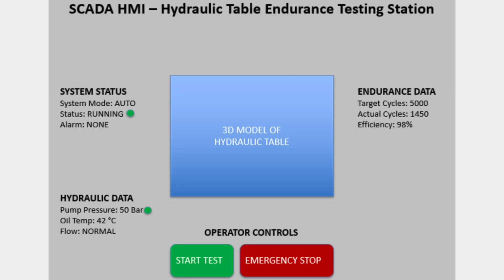Hello, I'll be presenting about the human machine interface of our SCADA-based endurance testing system. This is a simulated SCADA HMI design for academic purposes, but it is based on a real industrial SCADA architecture using PLC input and output. As you can see on the slide, the operators can monitor system status, hydraulic parameters, and test cycle counts in real time. All sensor data such as proximity sensor feedback and pressure values are acquired through the PLC and visualized on the SCADA screen.